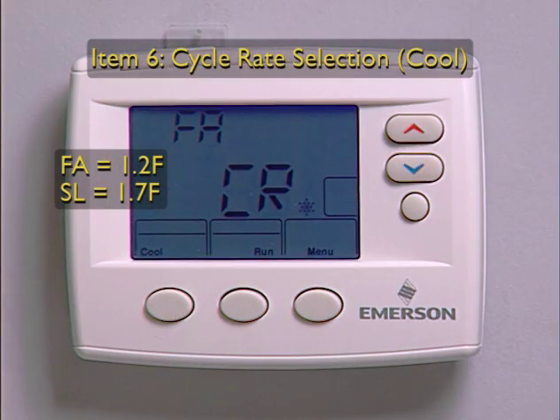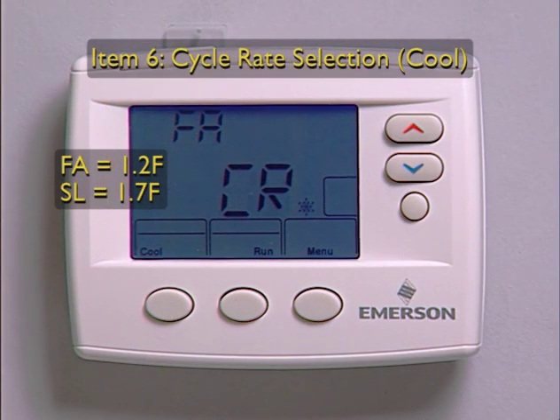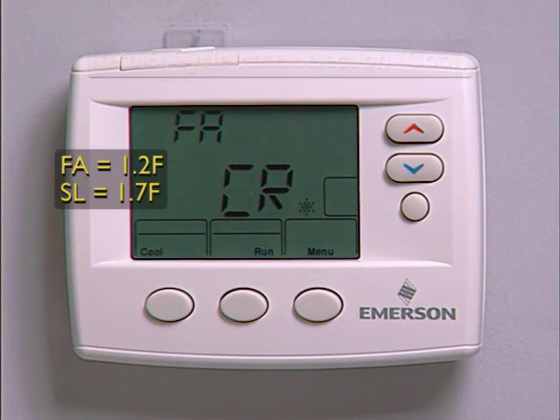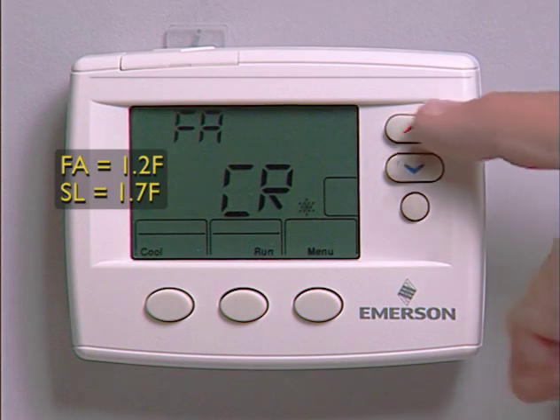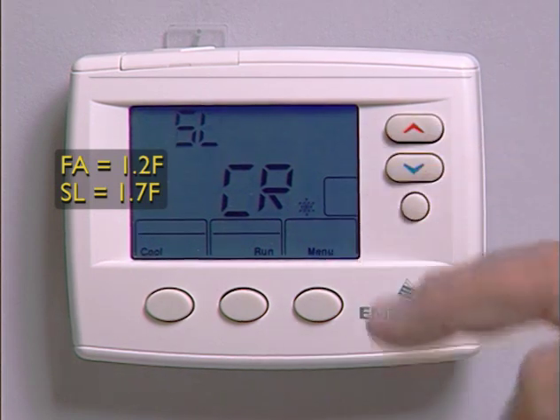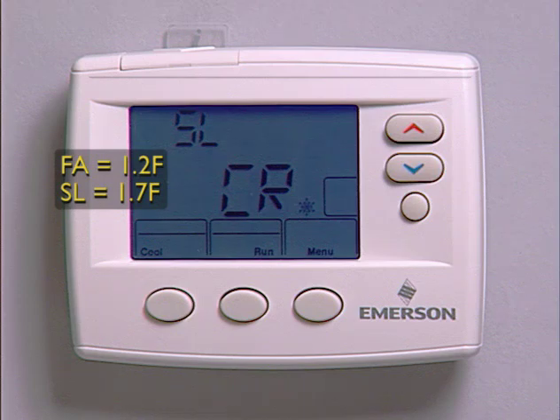Menu option 6 is the cycle rate selection option for the cool function with the default display of FACR and the snowflake icon, at about 1.2 degrees. Press the arrow keys to select the slow option of about 1.7 degrees if you want longer run cycles for dehumidification.